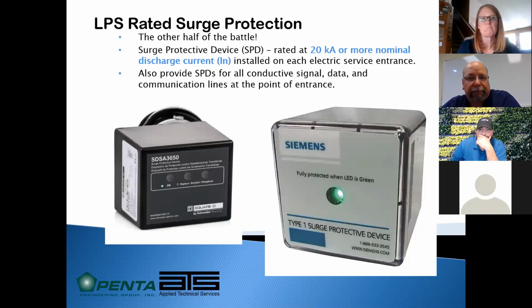So the rooftop lightning protection is really one part of a complete protection against lightning. Lightning-rated surge protection is the other half of the battle. So we want surge protection. The lightning protection on the rooftop is going to protect the building somewhat from a direct strike, but surge protection protects from adjacent strikes and energy traveling in on various service entries. And that needs to be not only on the electrical service entry, but also on any conductive signal path. So your data, cable, communication lines, phone lines.